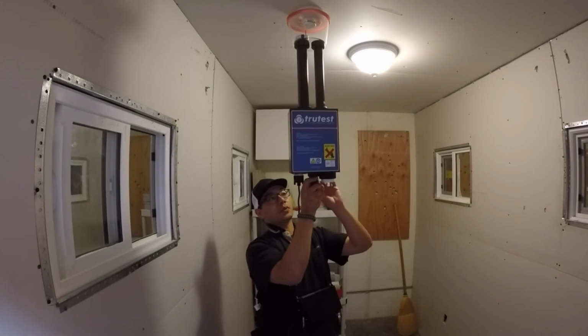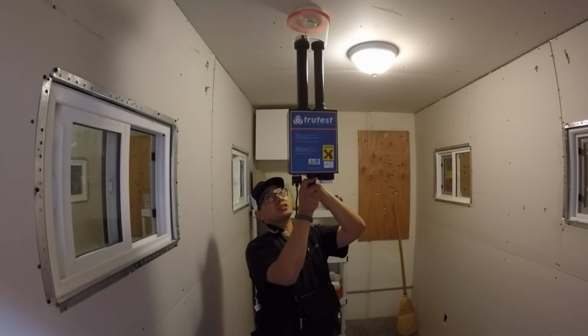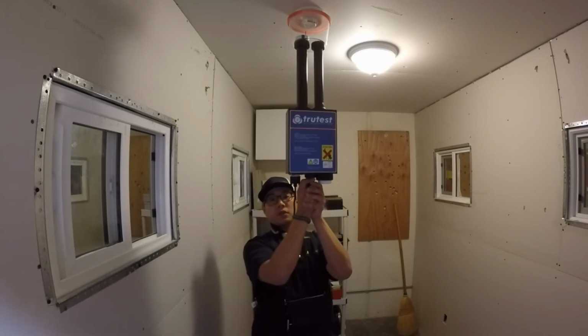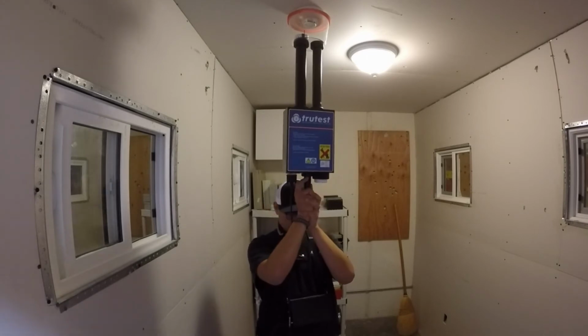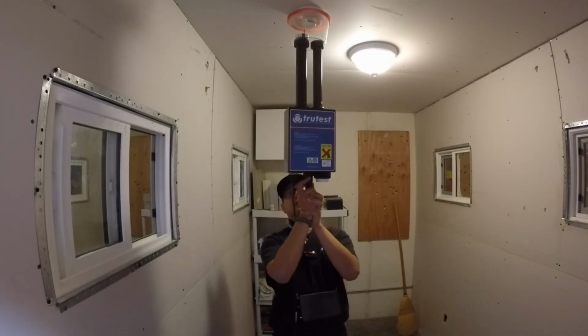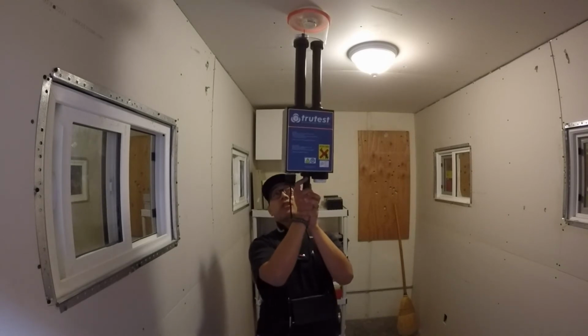So what you're hearing now is that thump. The machine is pressing the canister smoke and it's pumping in smoke into this chamber above. If you look in your screen, you'll see the percentage at the chamber. So right now the reading's at 0.05%. And it's just going to keep on pumping smoke into the chamber above. You're going to stop it when the smoke detector goes into alarm. And then whatever percent it's at, you record it and you put in your paperwork.